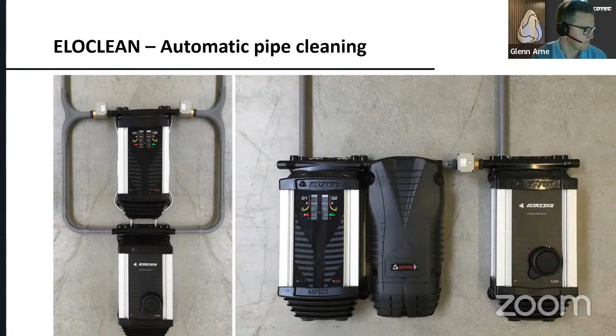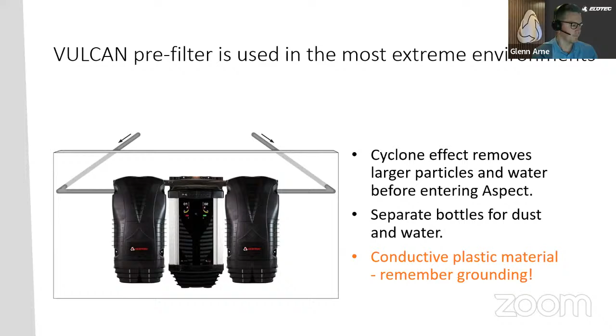Another accessory we have is the Vulcan pre-filter. It's used in the most extreme environments. This is a cyclone filter that removes larger particles and water before entering the Aspect, with separate bottles for dust and water. Remember, this is conductive plastic material, so remember the grounding. There is no power supply to this filter—it's a mechanical cyclone filter. But remember, this is also only needed in the most extreme environments. If it's very small and light dust particles, it won't be needed, since the filters inside the Elotec Aspect will take out the dust. It's only used for big and heavy particles.